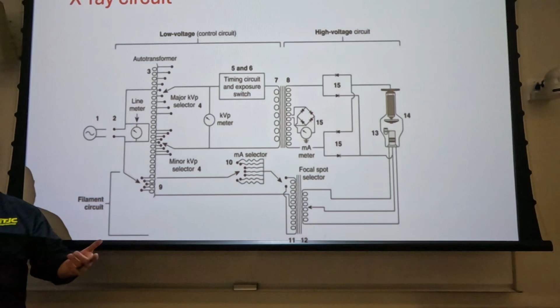Unless you're working with a single phase machine, line voltage compensation does not appear on your control panel, but it's built into the system and takes care of itself. So the computer in the machine automatically controls that, so you don't have to adjust it. If you're working with a single phase machine, you'll see that on the control panel.